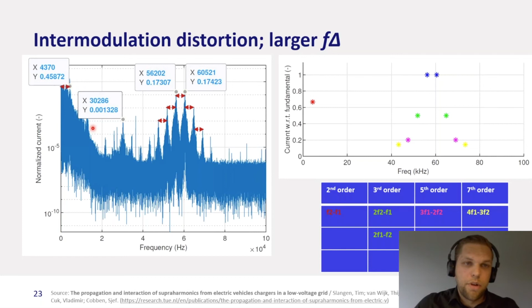Now, already at the end of my presentation, to conclude, we saw very interesting things. At first, in the measurements I did on the different electric vehicles, it was concluded that 8 out of 9 are a source of supraharmonic components, and that most have supraharmonic components within the human hearing range. So that's something that really should be considered. Propagation depends really on the grid impedance and on the device impedance. Taking away the grid connection resulted in different emission from the electric vehicles, and also, of course, will change the impedance of the PV and the battery inverters. But as mentioned, it is very difficult to determine the high frequency impedance of a device by just measuring or looking at it, because this possibly is also affected by the operation stage or the type of grid where it is. We looked at supraharmonic interaction.